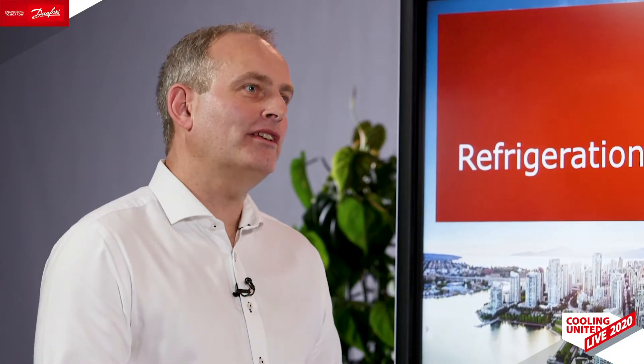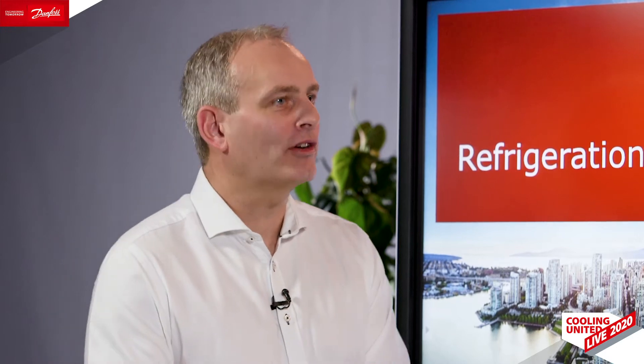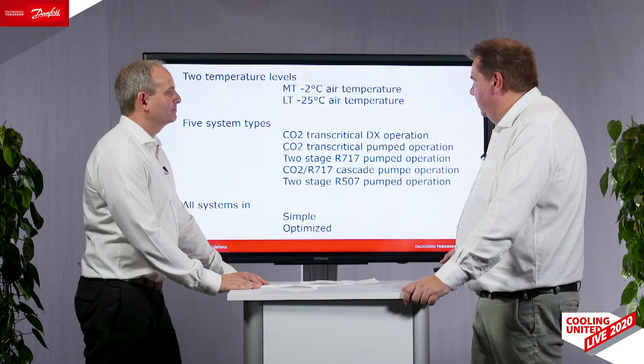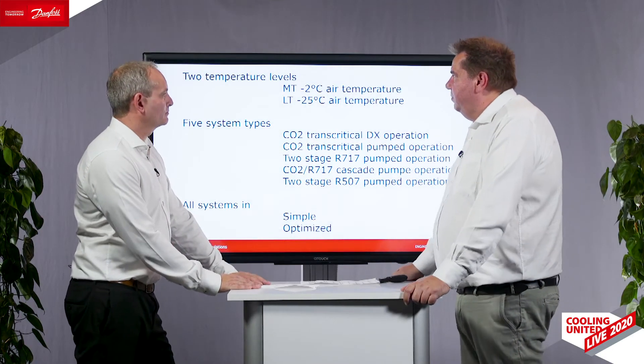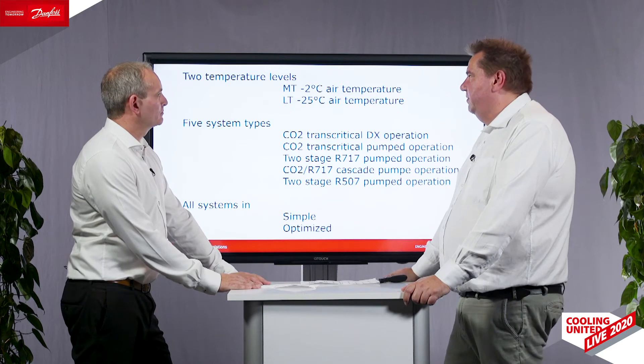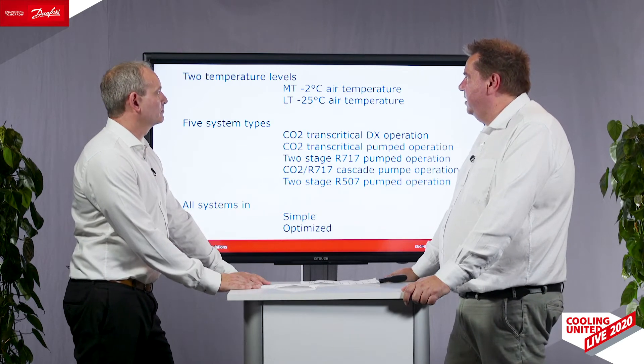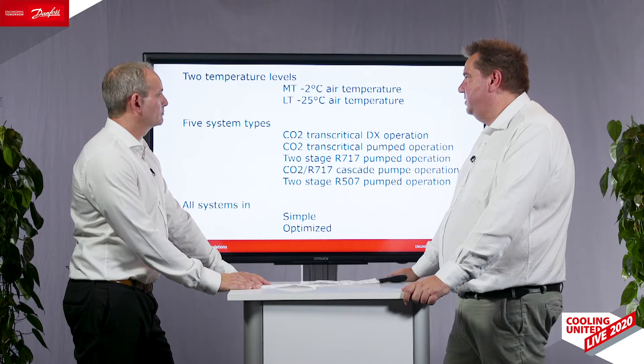Can you tell us more about the systems and the conditions under which the calculations were made? We started out saying that we wanted to model systems that had two temperature levels. We decided on a minus 2°C air temperature at the medium temperature and a minus 25°C at the low temperature. The evaporating temperature comes from this air temperature, but there's a difference in temperature difference from DX to flooded systems, and that gave us some differences.